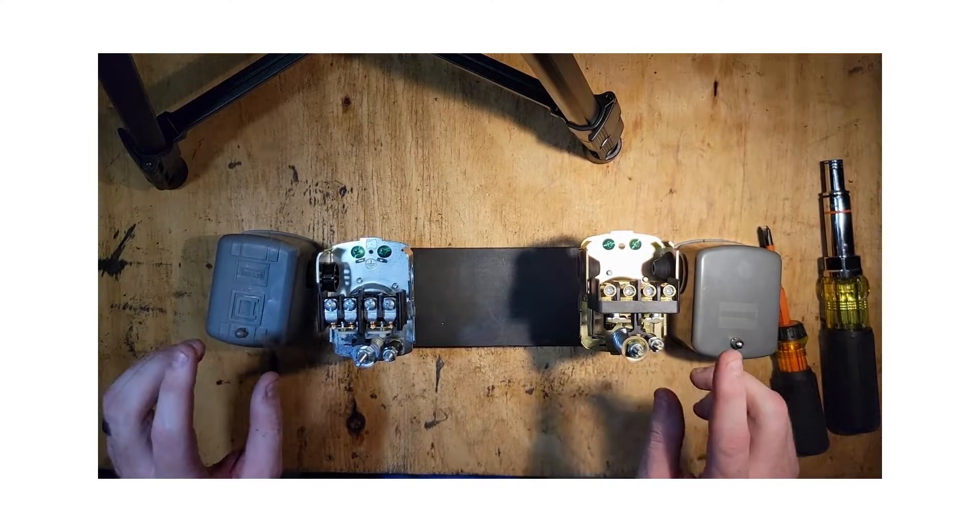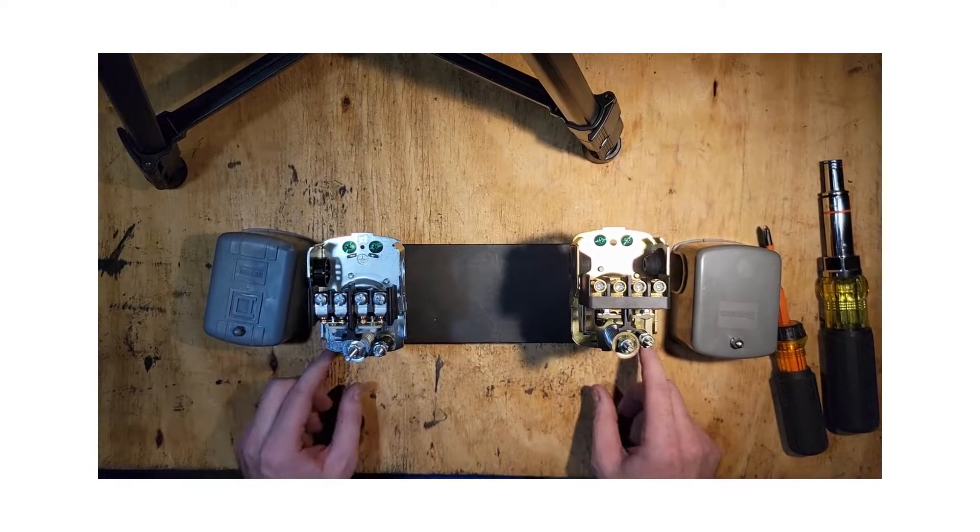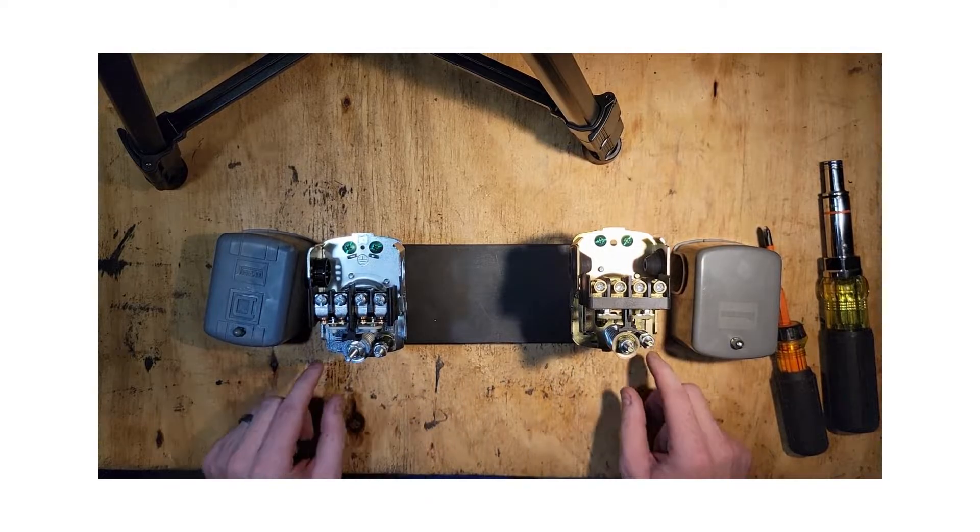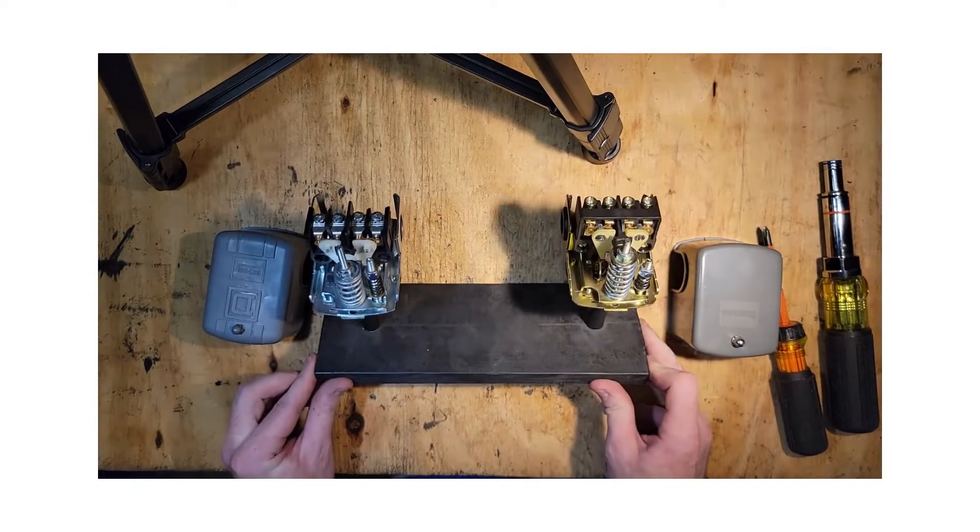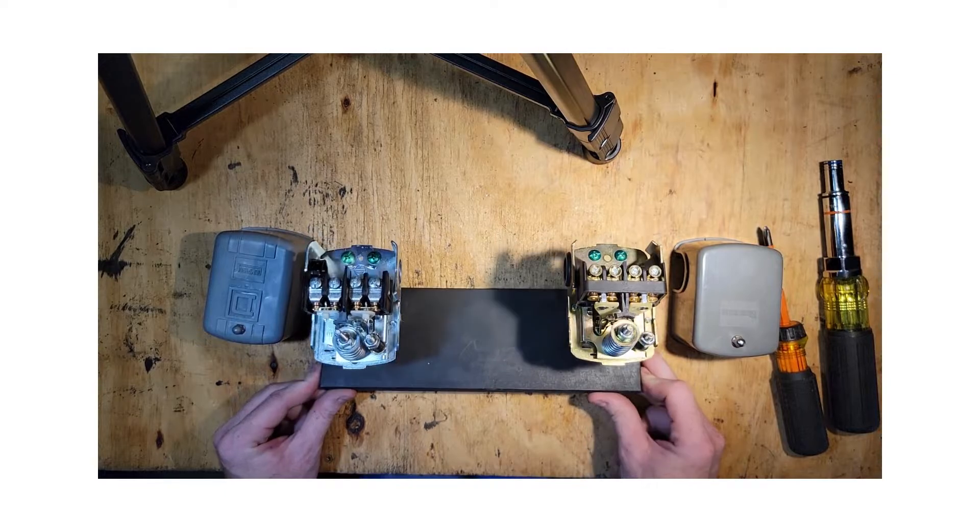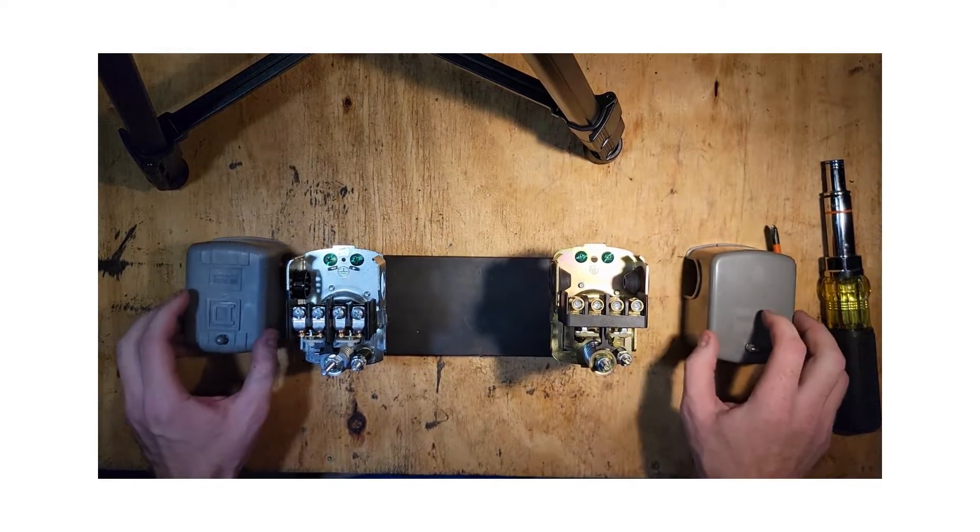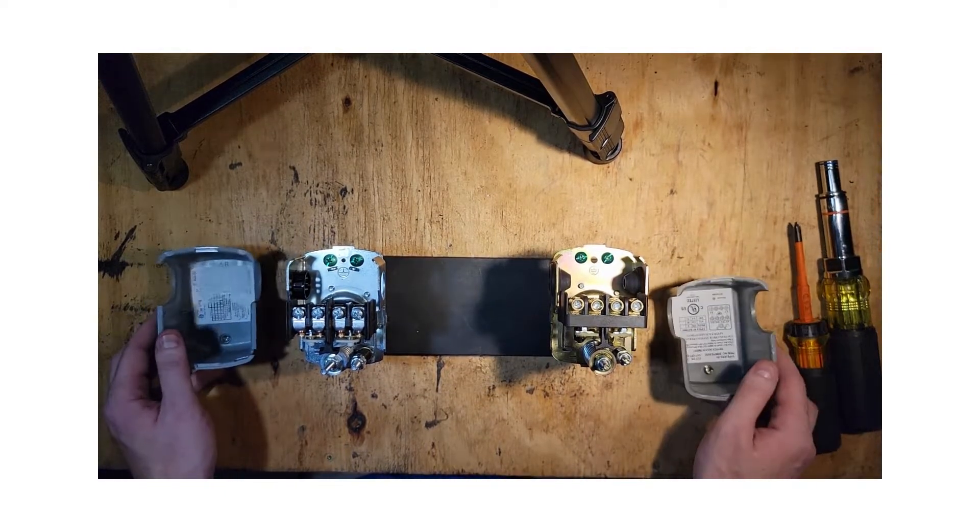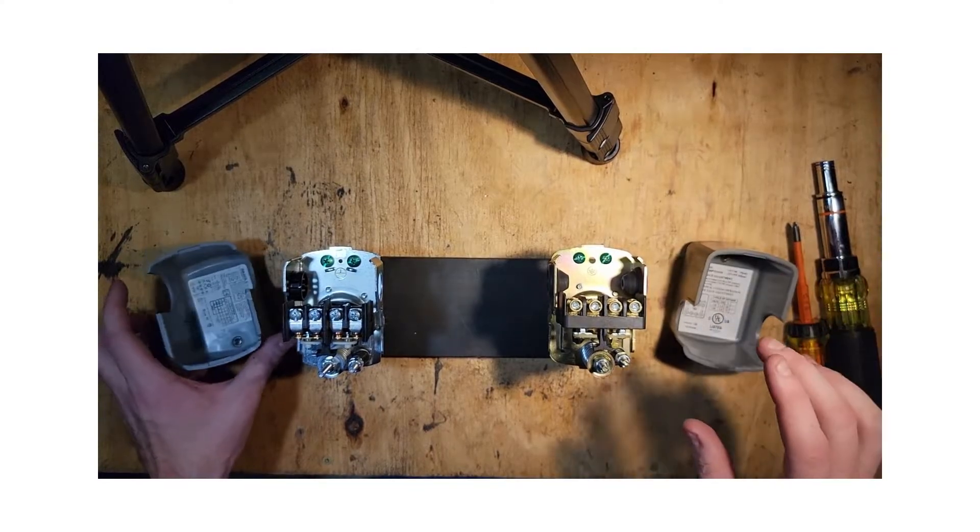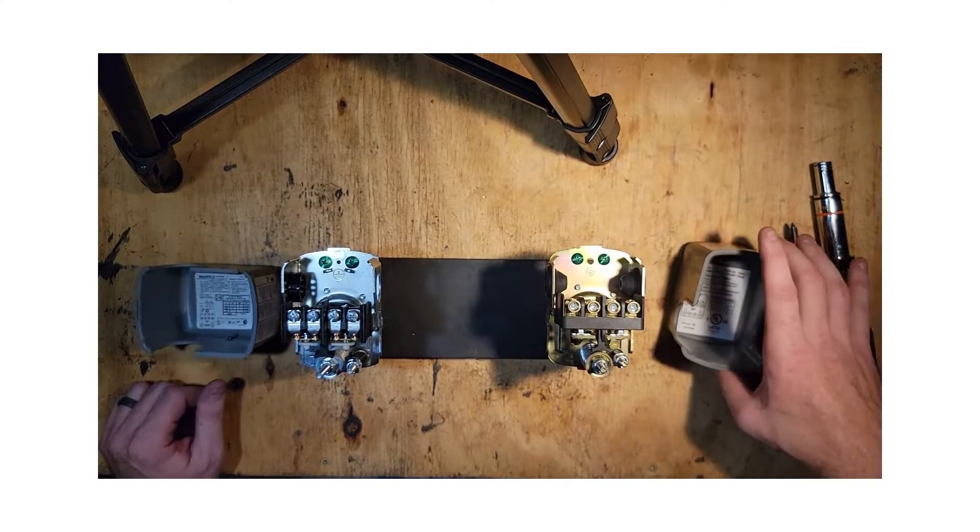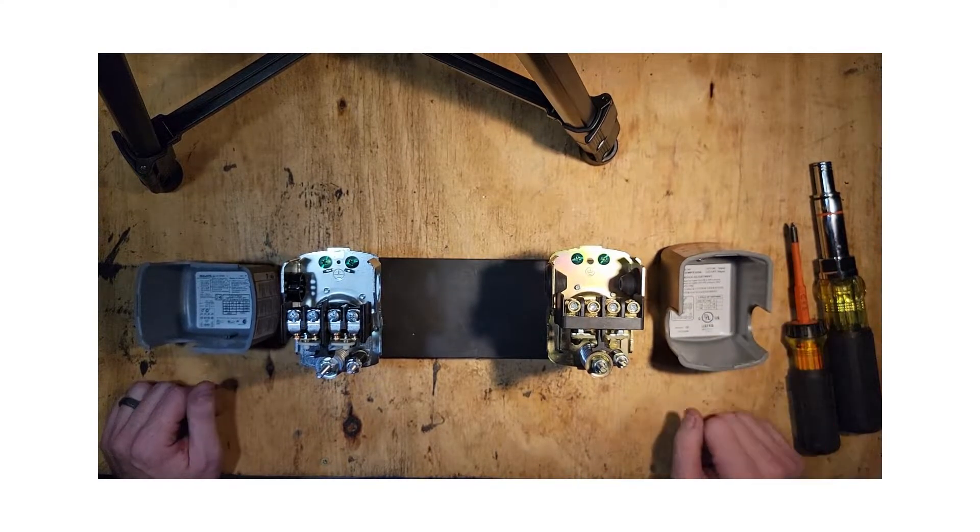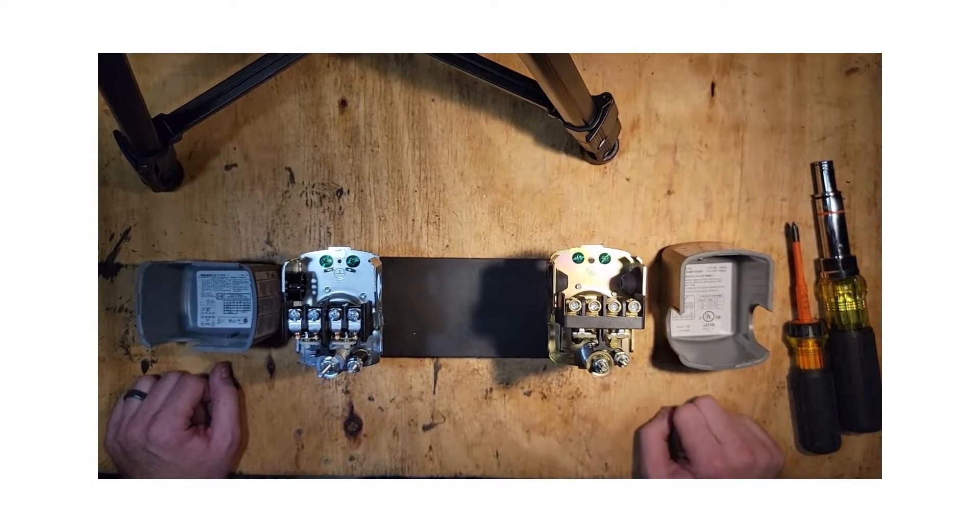Looking at these two switches you're going to notice two nuts and two springs. Each one does something different on the switch. If you look inside the cover of your pressure switch, assuming the sticker is still there, it actually provides you with the instructions for adjusting these switches.